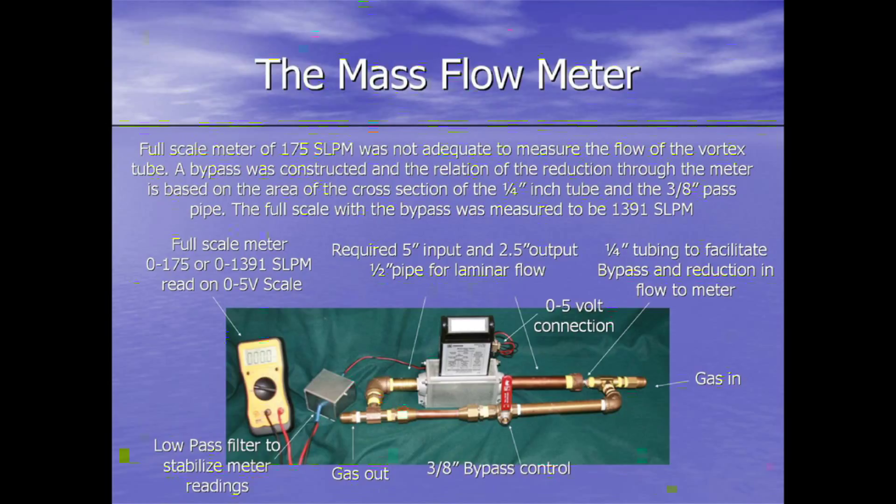I created the meter, as you see in the picture, with a bypass on it with a bypass control, which is simply just a valve, which allows me a change by a ratio of 7.947 to 1. So that the full scale meter reading on the voltmeter, instead of being 0 to 175, is 0 to 1391 standard liters per minute.